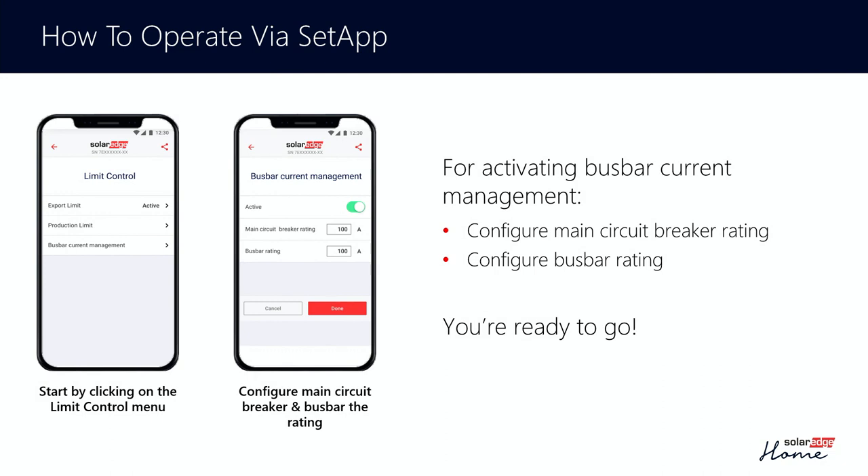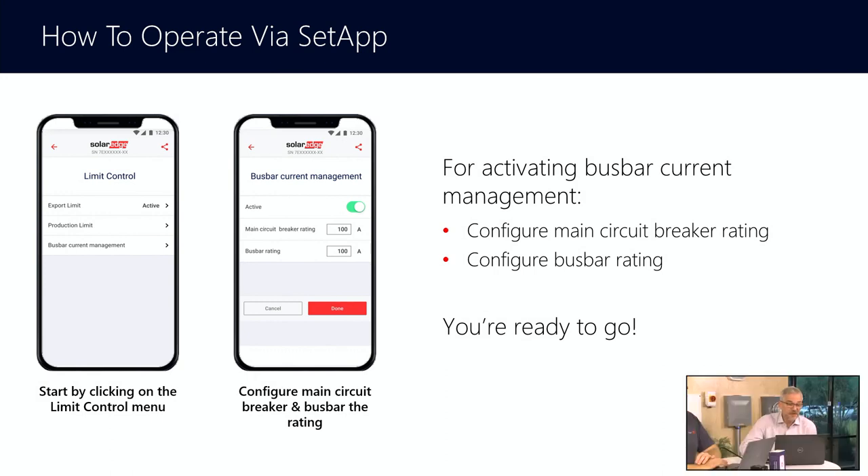In order to configure it, it is reasonably straightforward. There is going to be a page in SetApp which allows you to activate bus bar current management. It asks a couple of basic questions: how big is your main circuit breaker, have you derated it, and what's your bus bar rating. Based on that little bit of information, you activate bus bar current management and it will essentially enable the intelligence inside of the inverter to run that system.